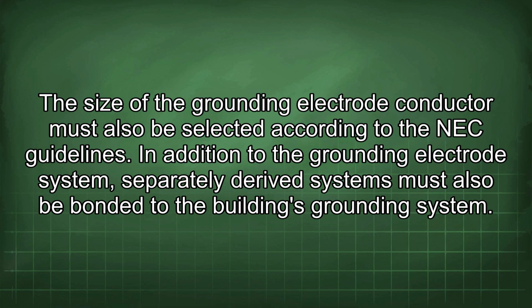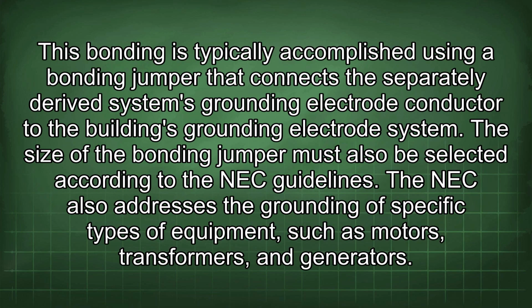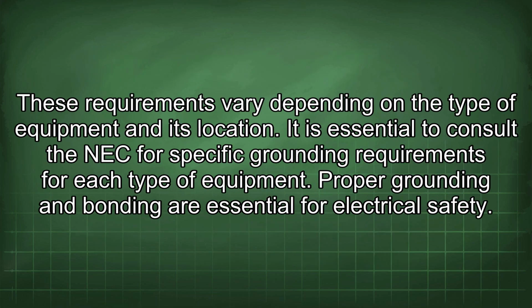In addition to the grounding electrode system, separately derived systems must also be bonded to the building's grounding system. This bonding is typically accomplished using a bonding jumper that connects the separately derived system's grounding electrode conductor to the building's grounding electrode system. The size of the bonding jumper must also be selected according to the NEC guidelines. The NEC also addresses the grounding of specific types of equipment, such as motors, transformers, and generators. These requirements vary depending on the type of equipment and its location. It is essential to consult the NEC for specific grounding requirements for each type of equipment. Proper grounding and bonding are essential for electrical safety.